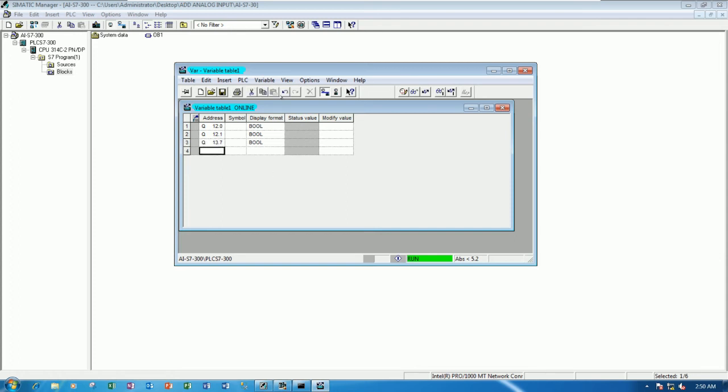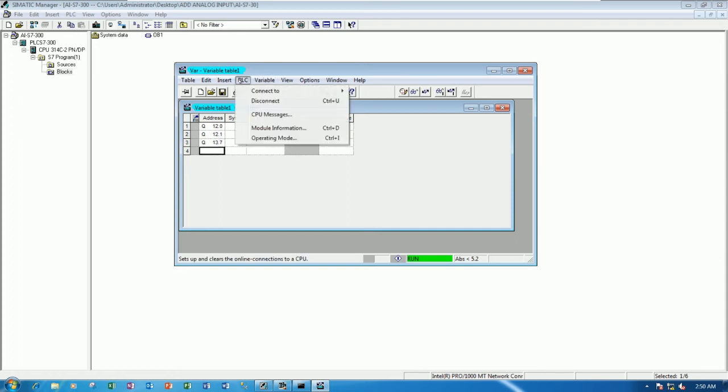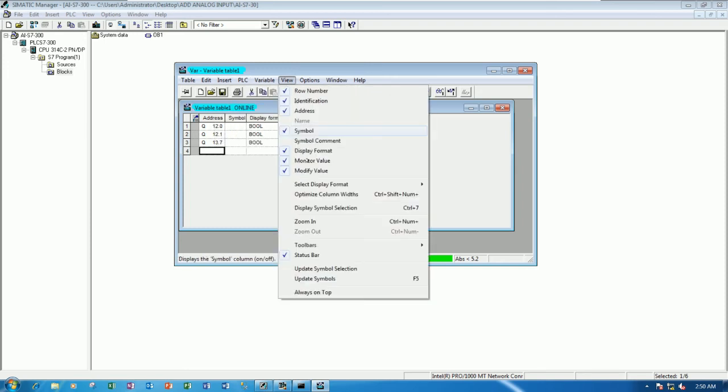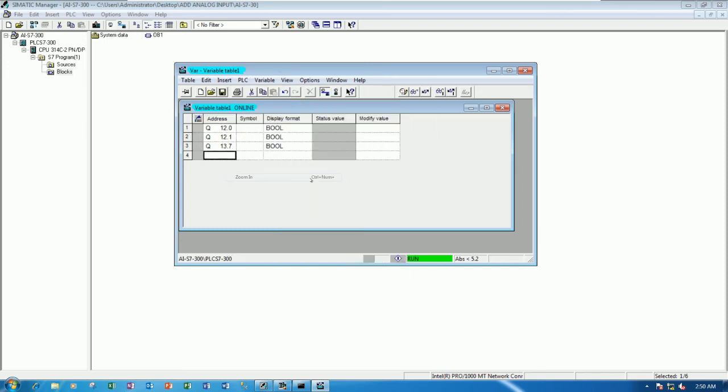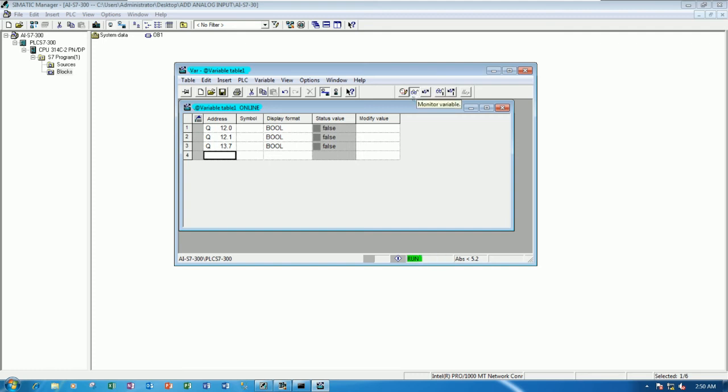So to test with the digital output, let's go to PLC and then go to the monitor, modify variables. And it will start from Q12.0, Q12.1 until Q13.7, right? And I will zoom a little bit. And then we can monitor by push this button. And then we can force the signal also.